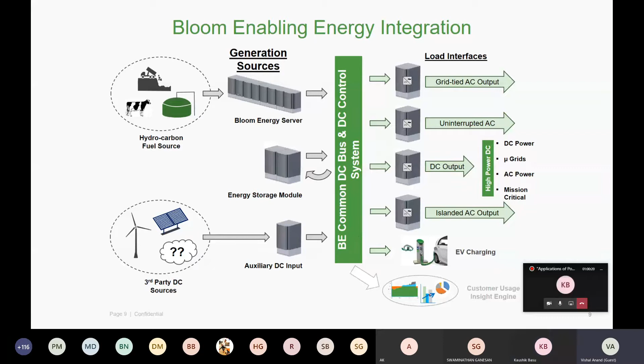This is a typical application of a grid parallel fuel cell system, where the fuel cell system along with the inverter is tied to a generalized grid. This is installed at the end user facility where the loads are located locally, as shown here. Since this is a grid-tied output, whenever the grid is not available, even if gas is available, we still cannot power the load because the grid is not there.